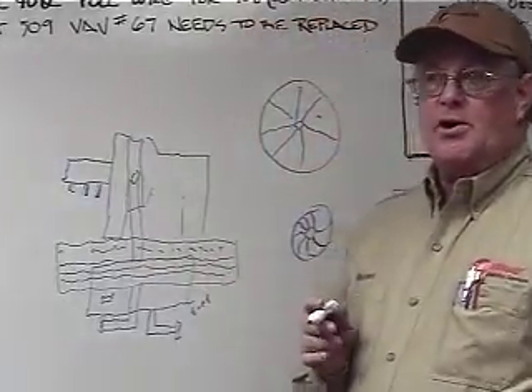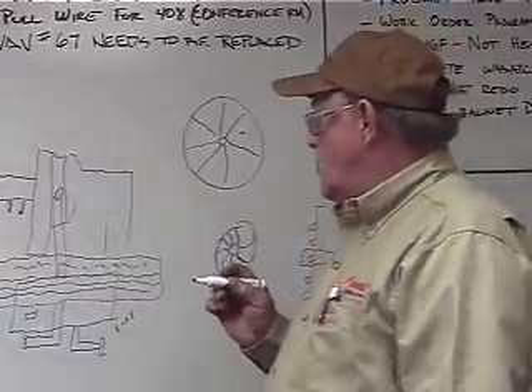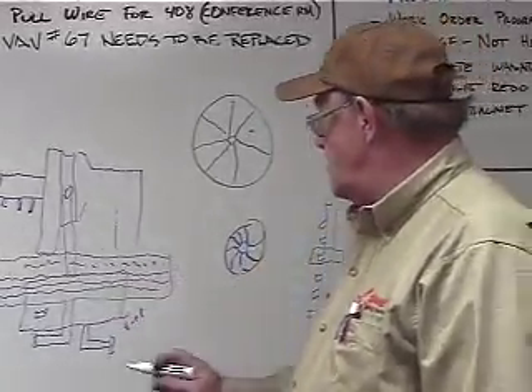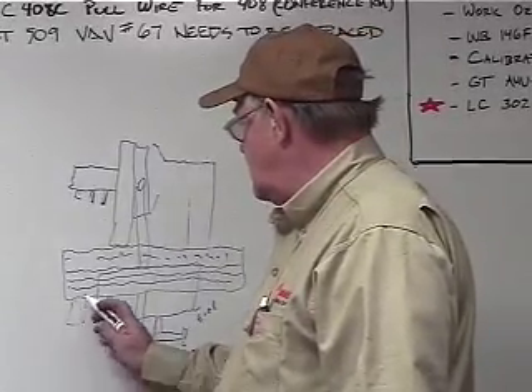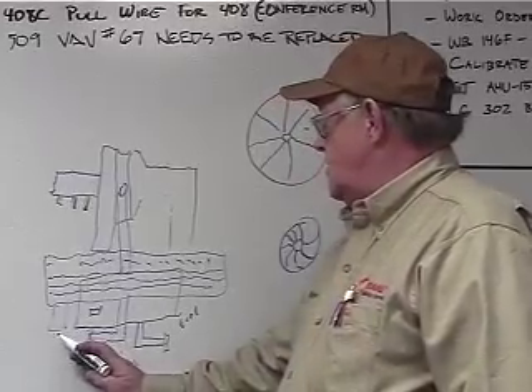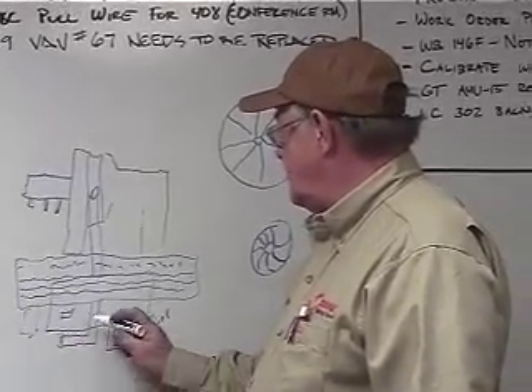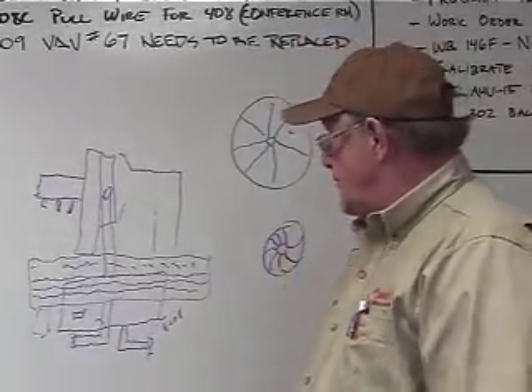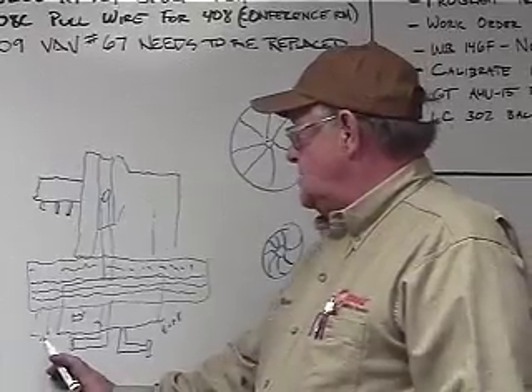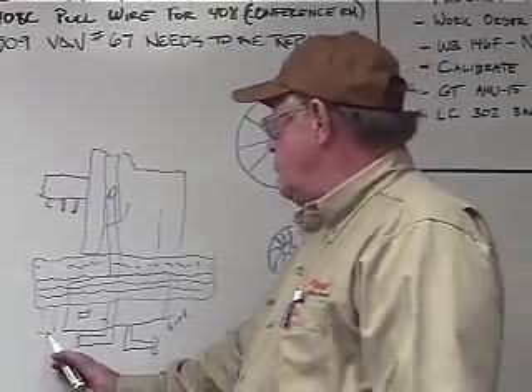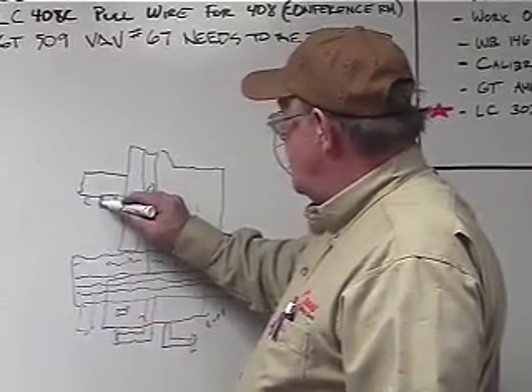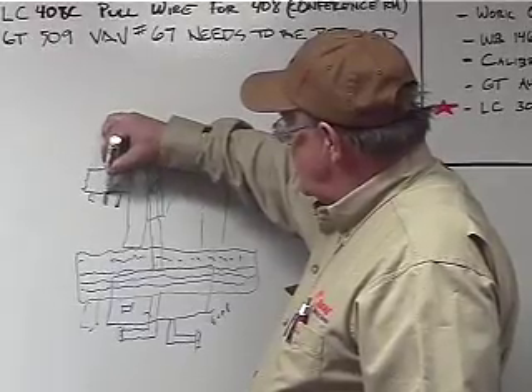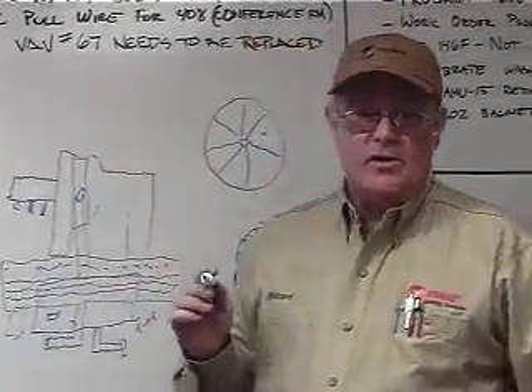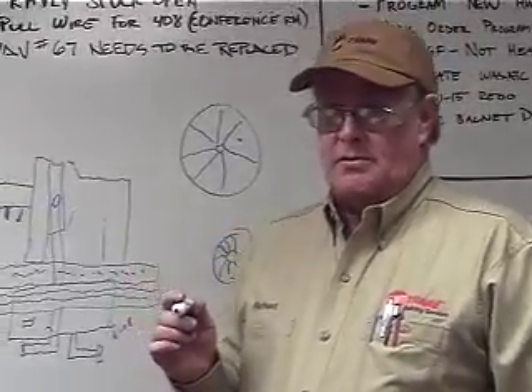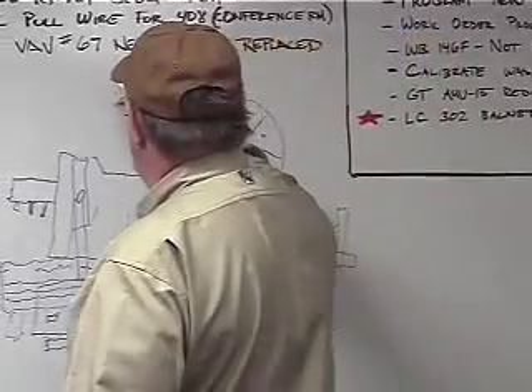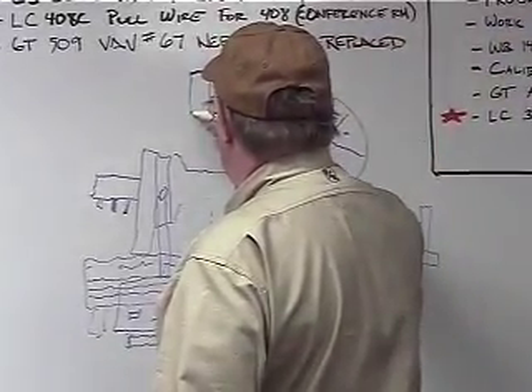The center line is what we call a refrigerant cooling line. What happens is in your oil sump, which is down here underneath the condenser, the oil sump actually has a refrigerant pump that comes off the liquid line of your condenser. On this sump there's a refrigerant pump. So that's going to pump liquid refrigerant up to this line right here. On this line here, there's going to be a little orifice plate in there. Does anybody know what this orifice plate does? Okay. What this orifice plate looks like is, we'll just kind of give a general idea of what it is.